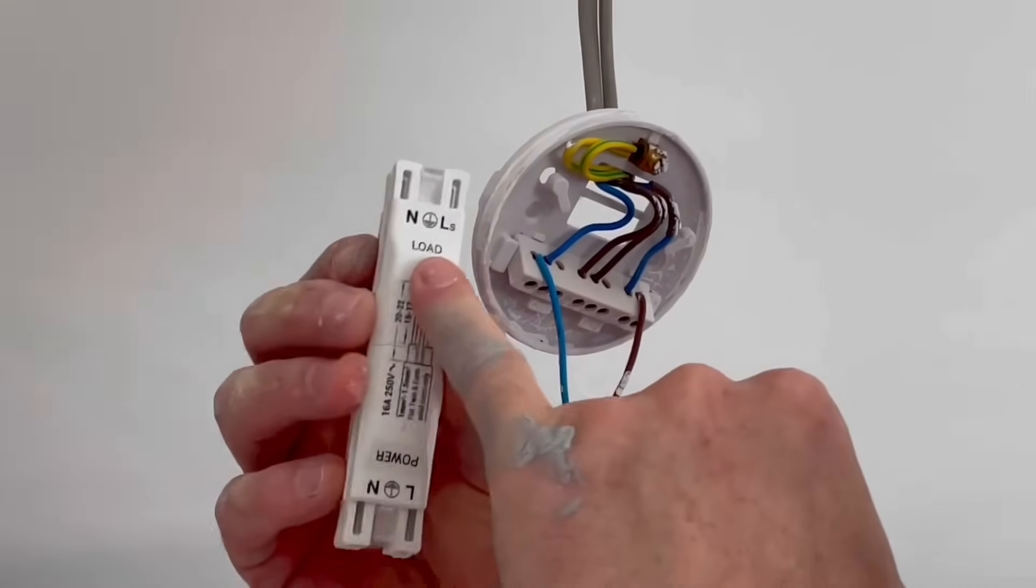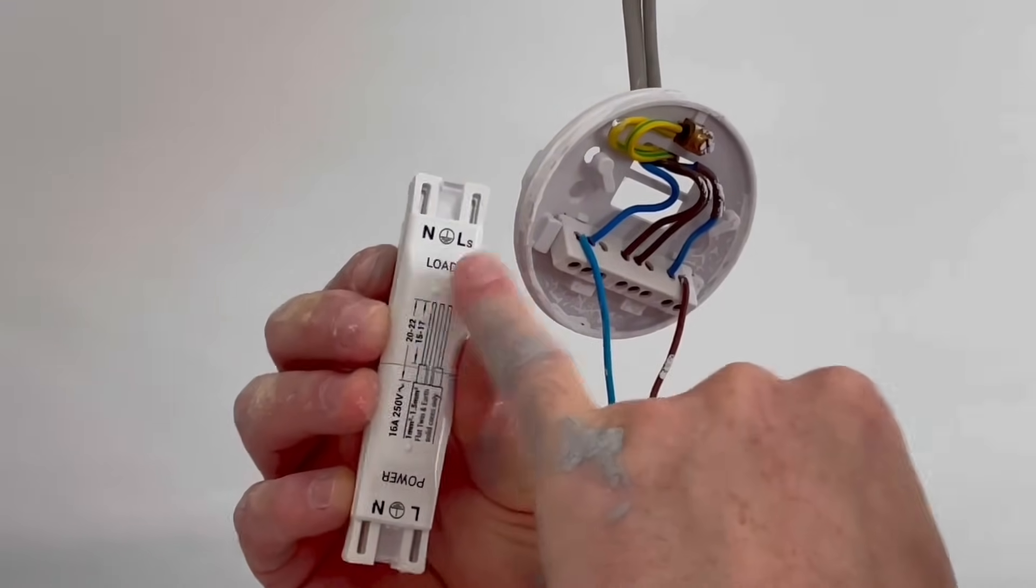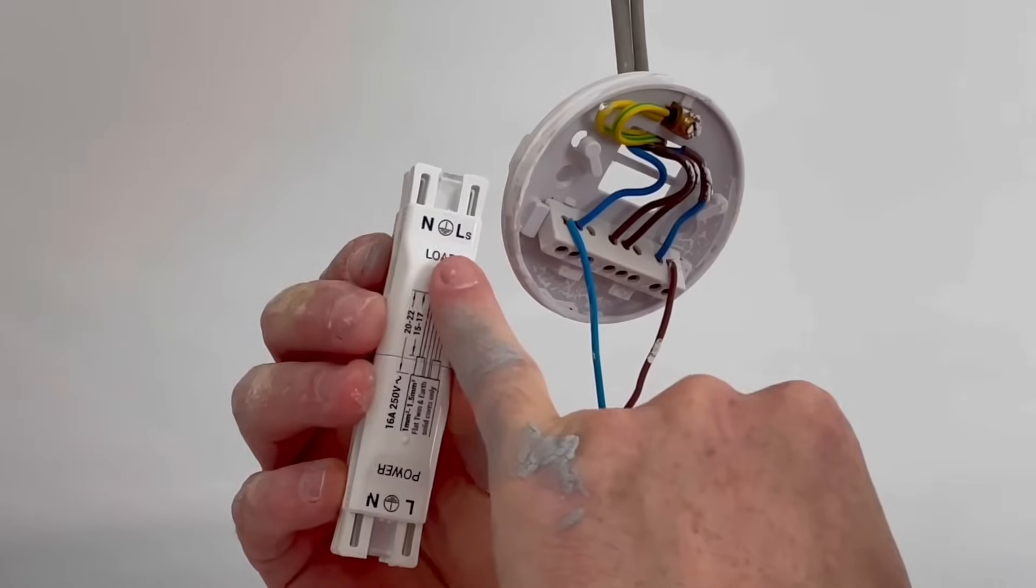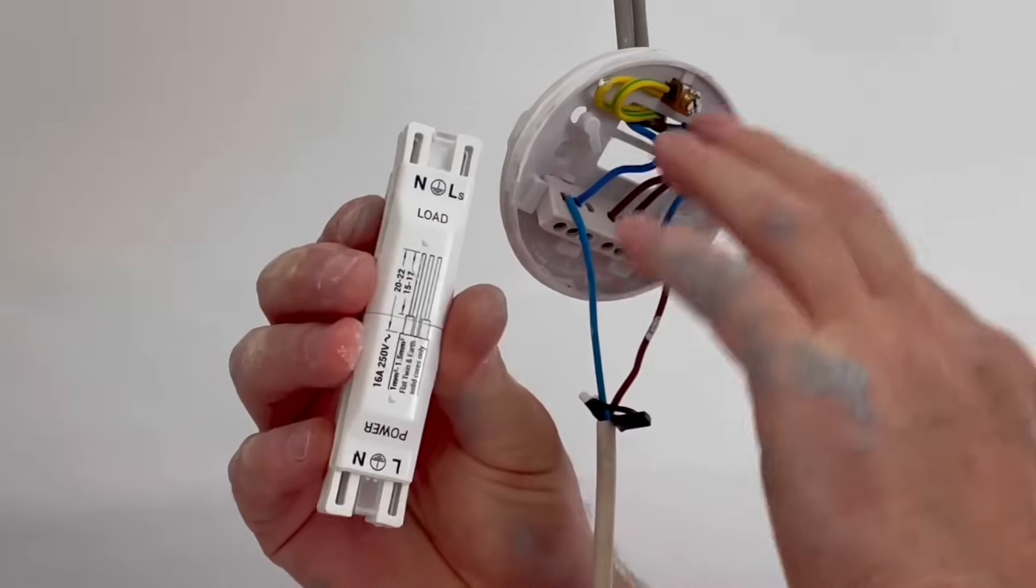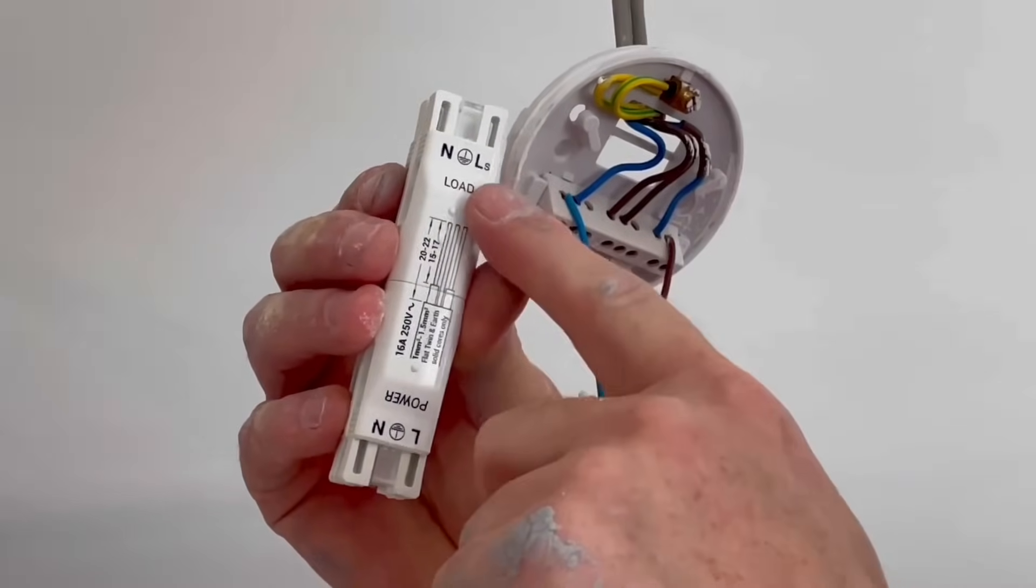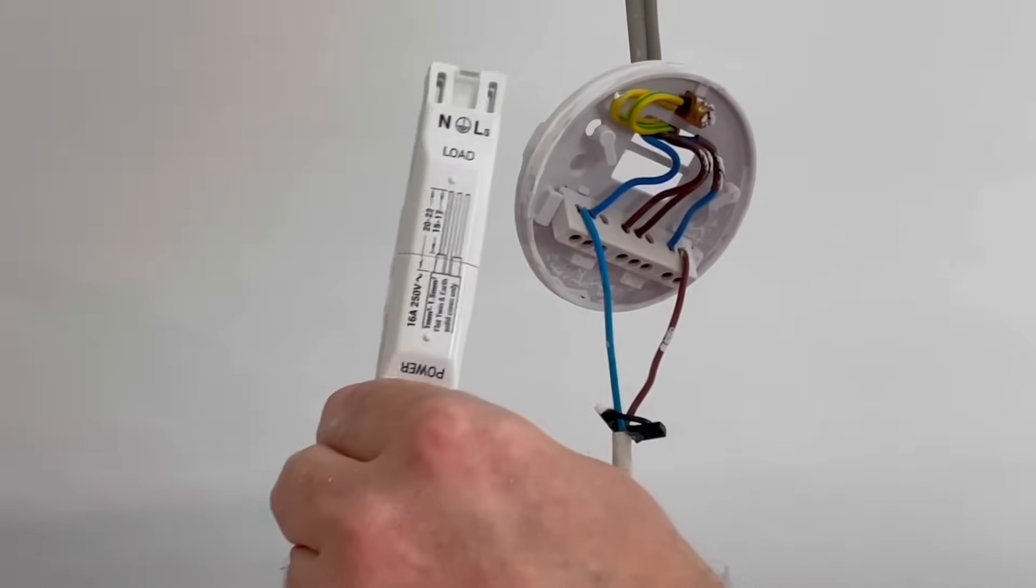And then our new cable which comes down to our LED light or load will have our switching line, neutral and CPC. I've already connected that into the LED light fitting and it just clips into here. So let's take the connections out of our ceiling rose and make them into here before we pop this into the ceiling and we can fit our LED light fitting.